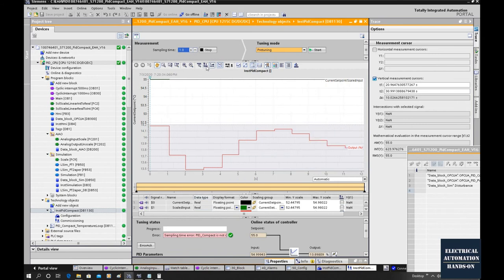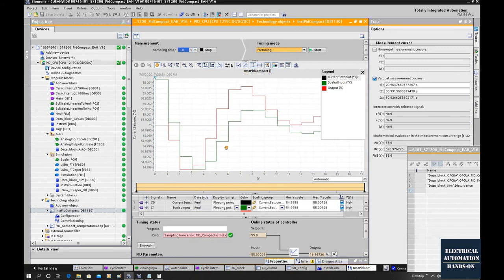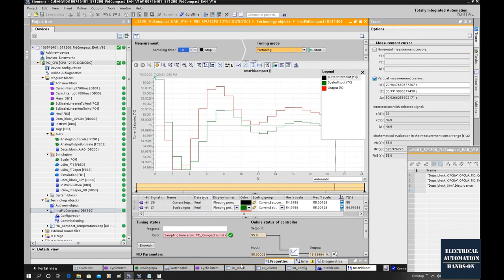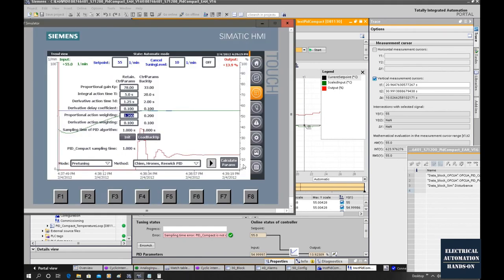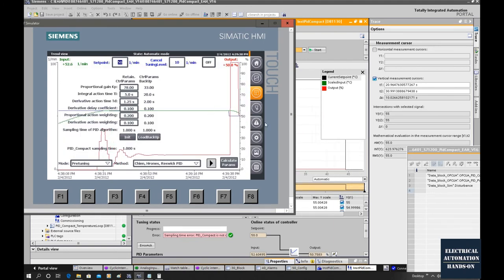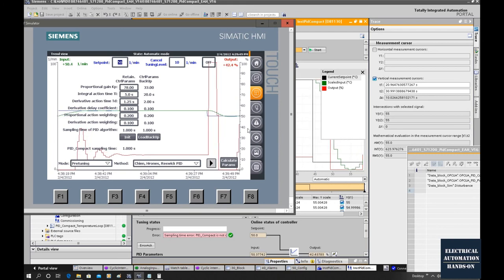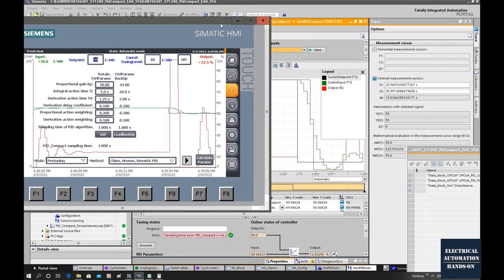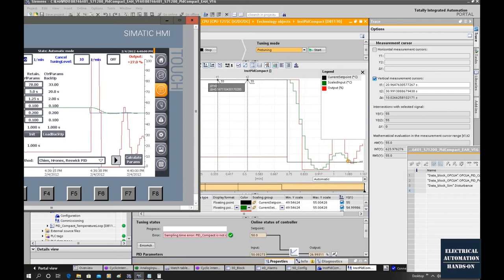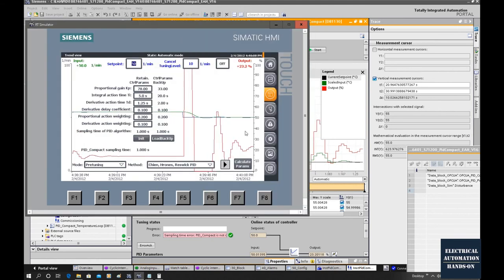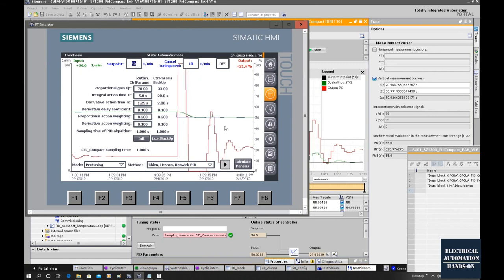Let's go back to this online trend. We will see the specific values of the process and control signals. This is the trace curve from the TIA Portal, which is built inside the PID controller. Currently the process has reached our setpoint. Let's set a new setpoint of 50 and see this transition. From the right side, we can see there is a little bit of overshoot there, but the value is really small. It looks nice. We can see there's a little bit of overshoot, so we can optimize the PID parameters and fine tune a little bit.